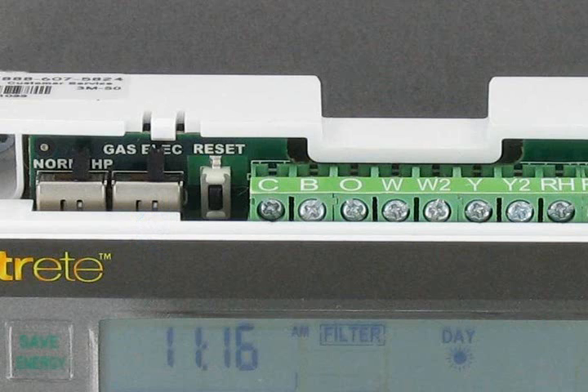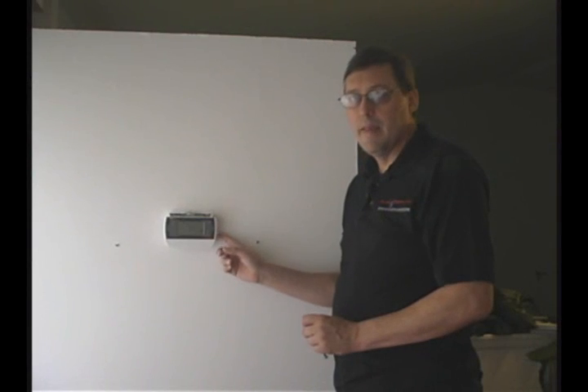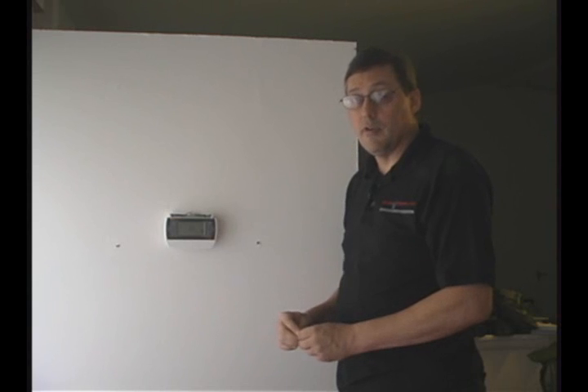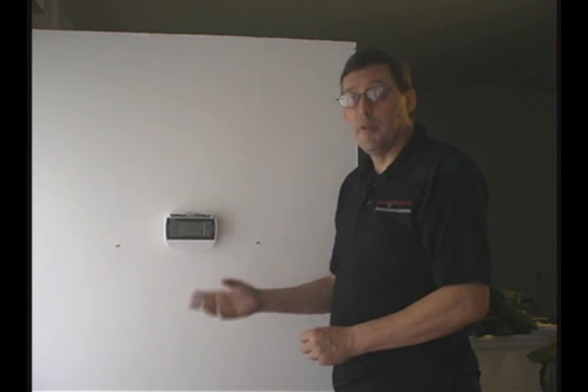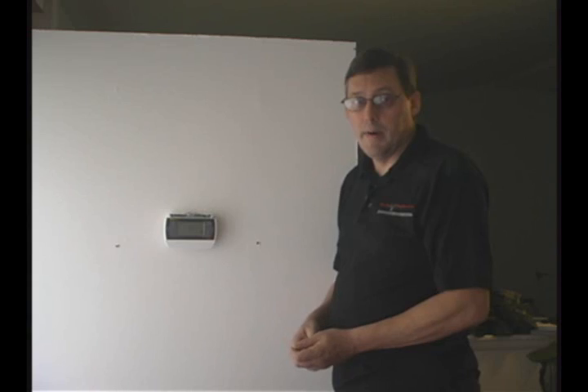The first one, the normal heat pump, you switch to decide whether you have a normal system or a heat pump system. What will be the dead giveaway for a heat pump system is that you'll have an O or a B wire, most likely an O wire, which will say that you have a heat pump. The other way is that when you tested the system before you put it in the thermostat and you put it in heat and you go outside and the compressor outside is running and it's blowing cool air out, then you know it's a heat pump.